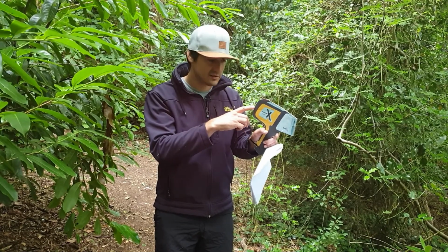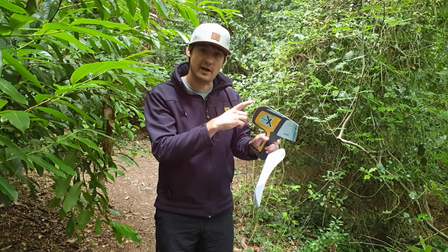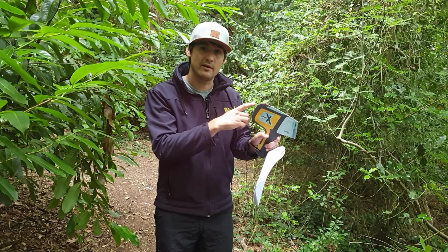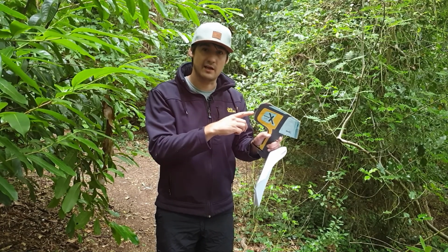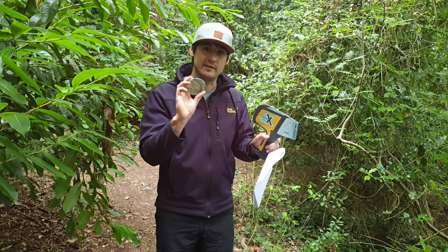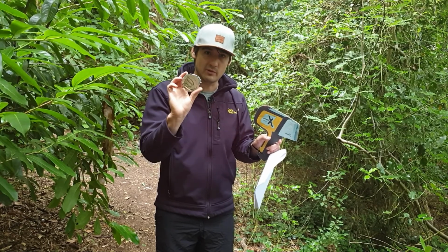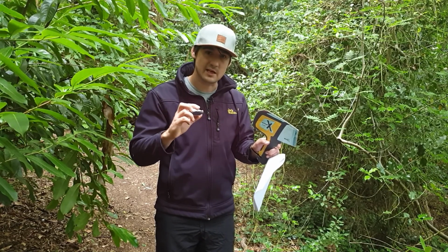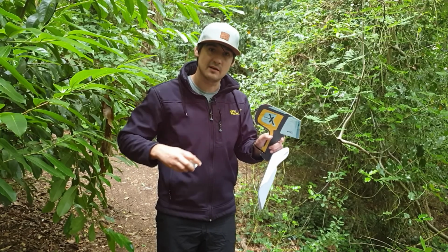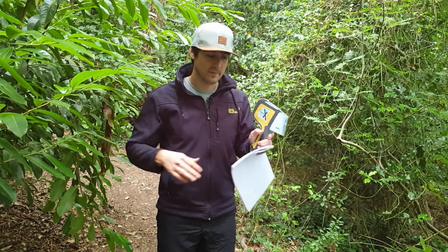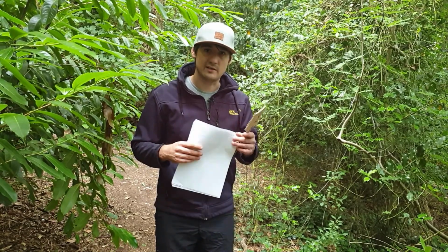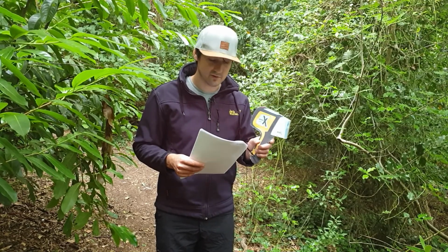So just check the screen on the back to see if the calibration check has passed. And once that's passed, just look on the top left of the screen and it should say reading 1. So your very first reading of the day is your calibration check via the titanium disc, either the portable titanium disc or the titanium disc which is housed within the docking station of the XRF. So either way you can calibrate the XRF via this route.